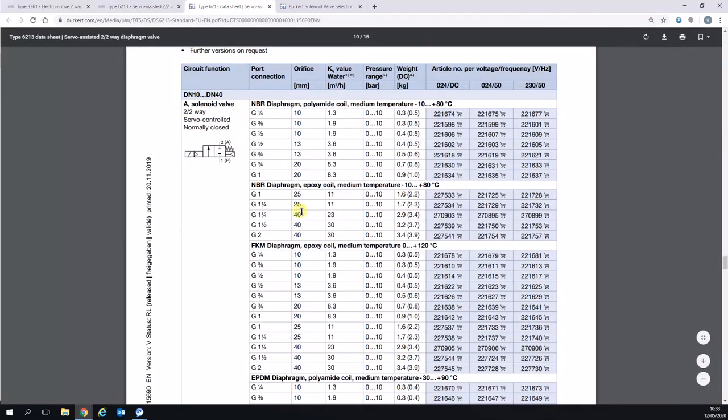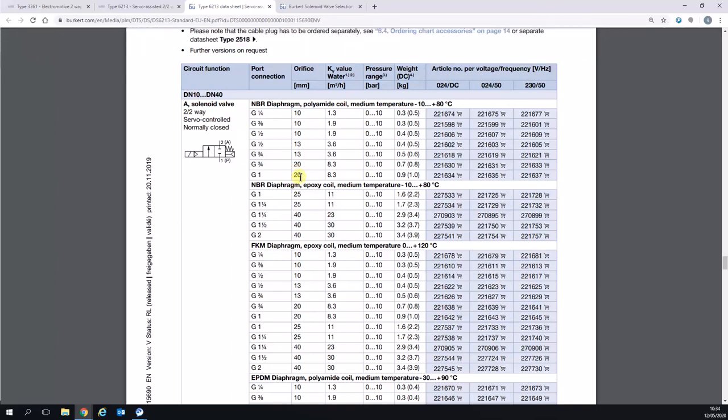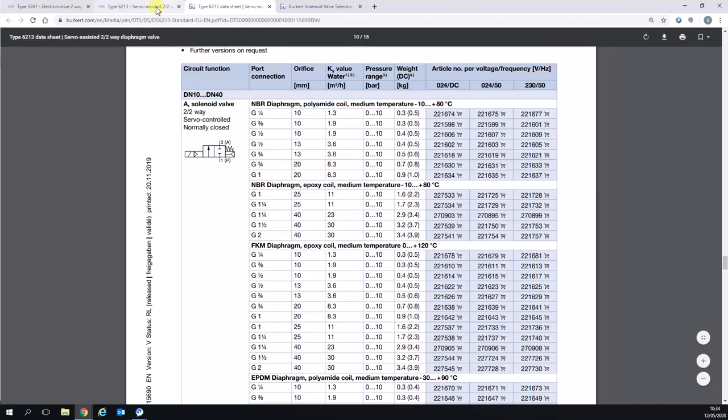When we go back to our data sheet, you can see that we could select the one inch valve with a 20 millimeter orifice and potentially make the valve a little more competitive. Or if the customer allows it, we could even go to three quarter inch with a 20 millimeter orifice and achieve the same KV. That would make the valve even more competitive.